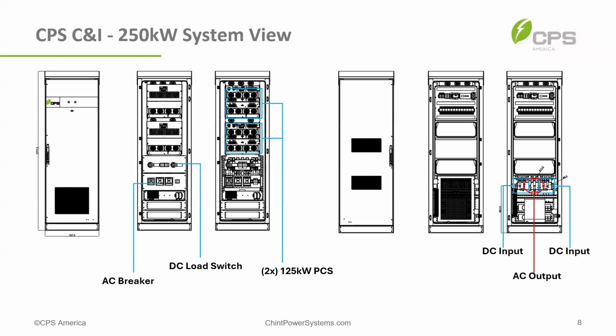But when you move up to the next step, to the 250, now each 125 is controlling its own battery cabinet. So if one of those goes down, you still have the other battery cabinet. It's hard to implement on a really small system, but we still have it implemented once you get to that 250.